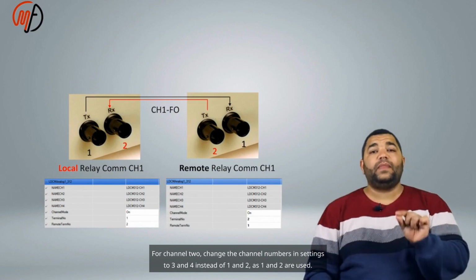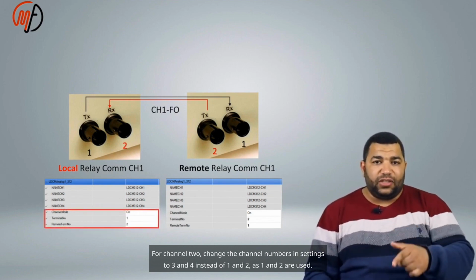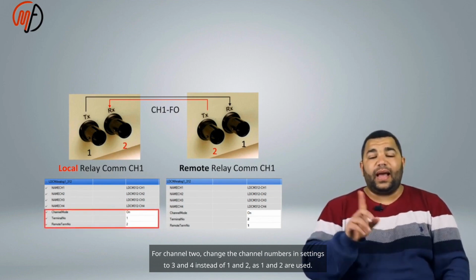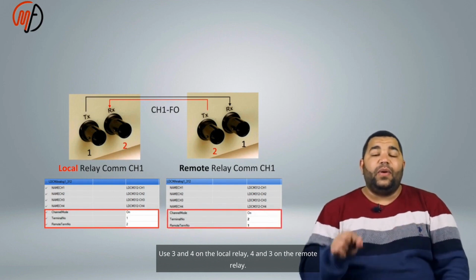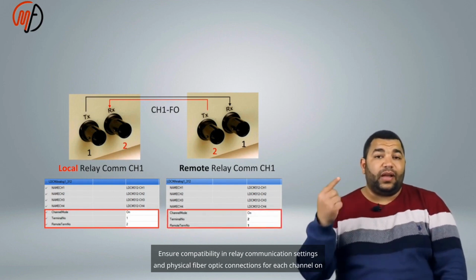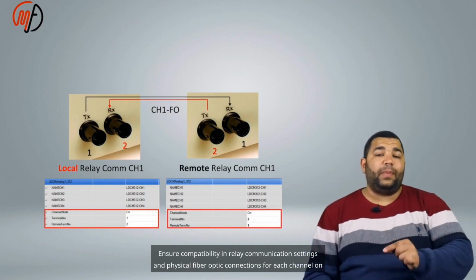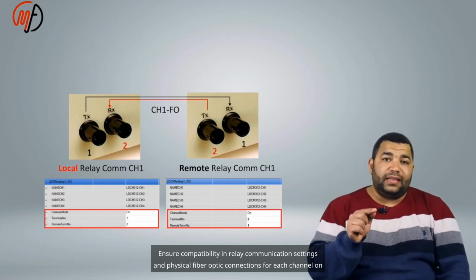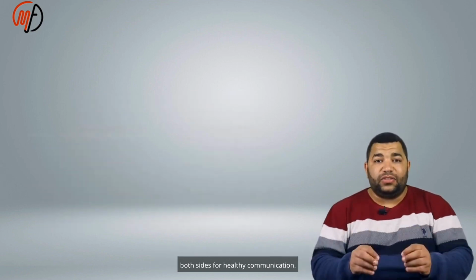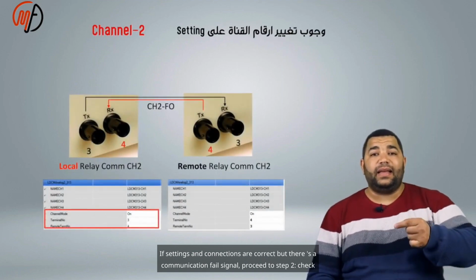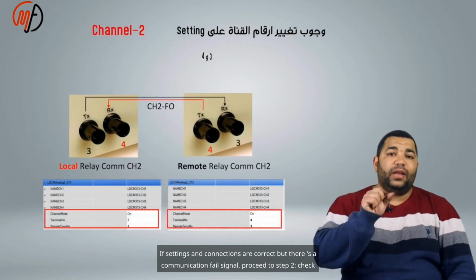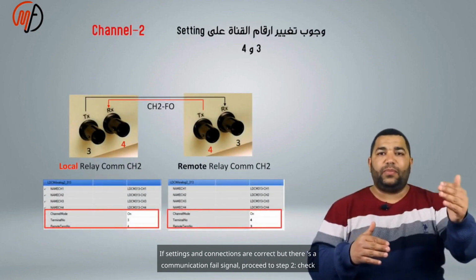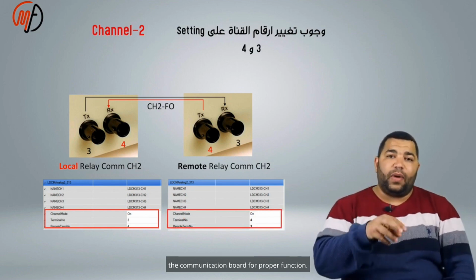For channel 2, change the channel numbers in settings to 3 and 4 instead of 1 and 2, as 1 and 2 are used. Use 3 and 4 on the local relay, 4 and 3 on the remote relay. Ensure compatibility in relay communication settings and physical fiber optic connections for each channel on both sides for healthy communication. If settings and connections are correct, but there's a communication fail signal, proceed to step 2. Check the communication board for proper function.